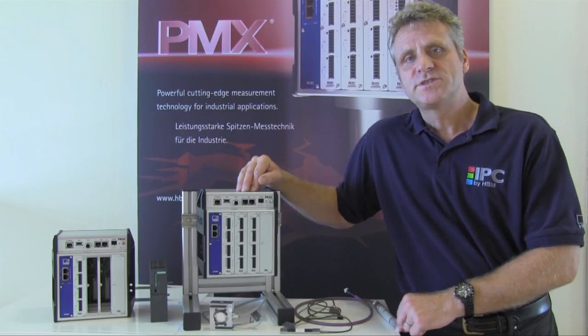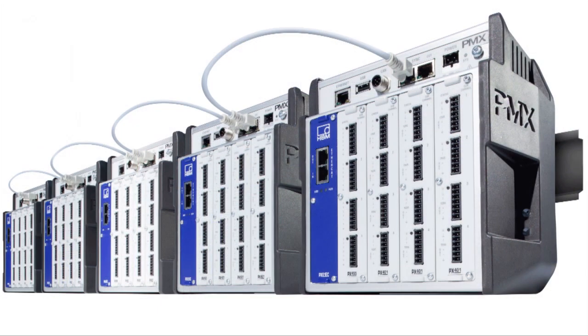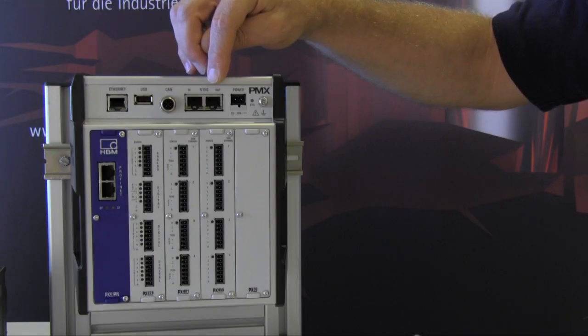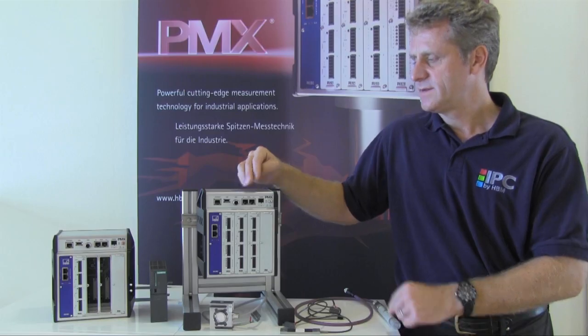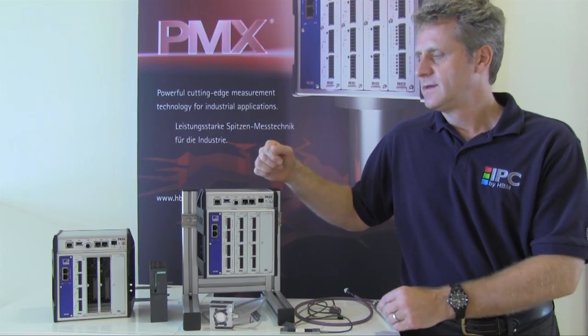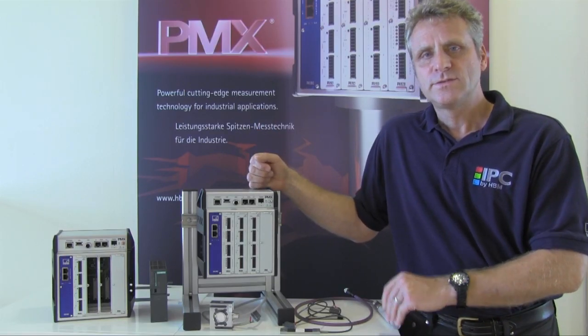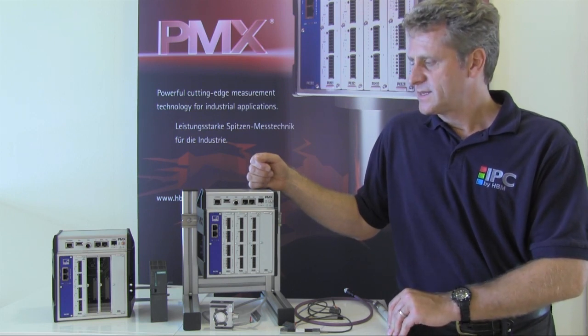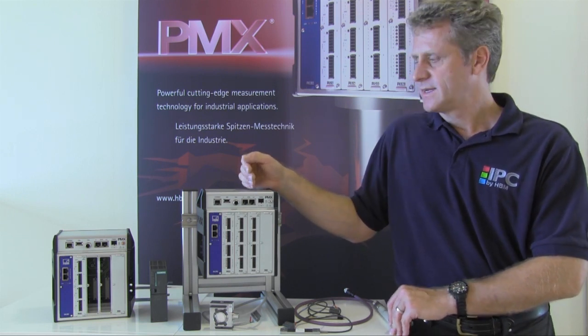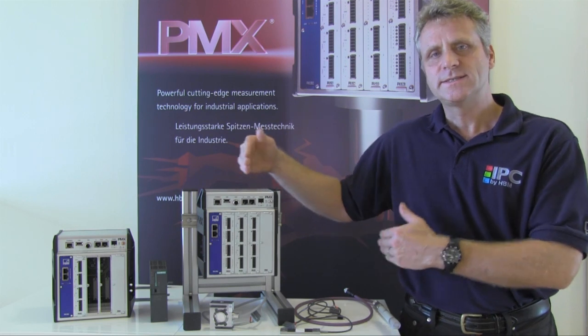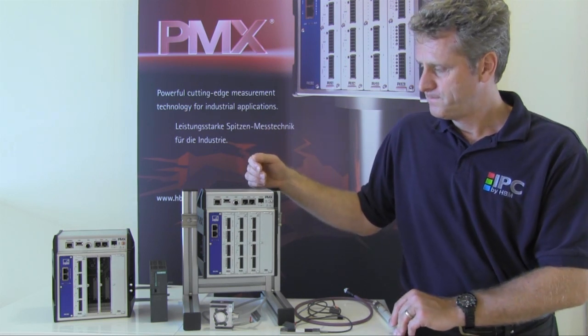If several PMX amplifiers need to be synchronized, this can be done with the RJ45 sockets. The carrier frequencies and timestamps of the individual measured values for all synchronized PMX devices are synchronized. The maximum number of devices is 20, and the distance between the individual devices is 30 meters.